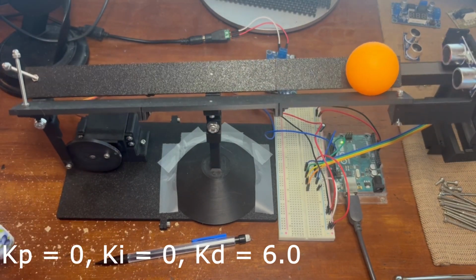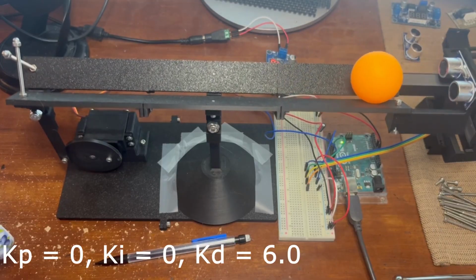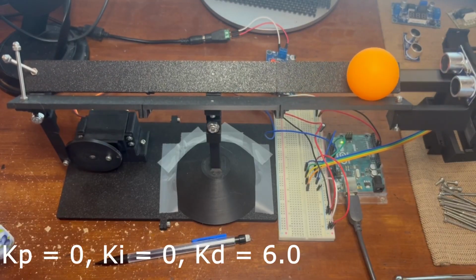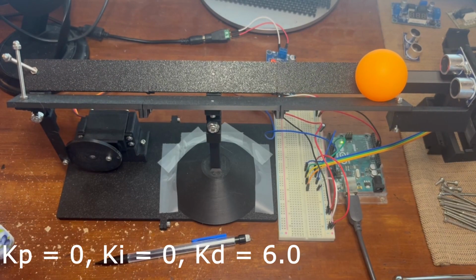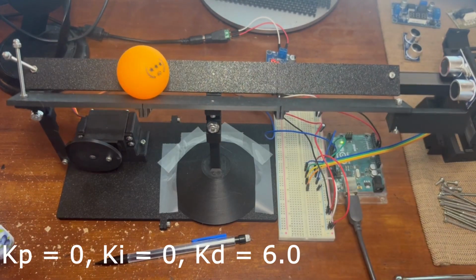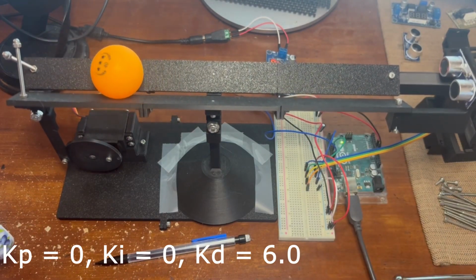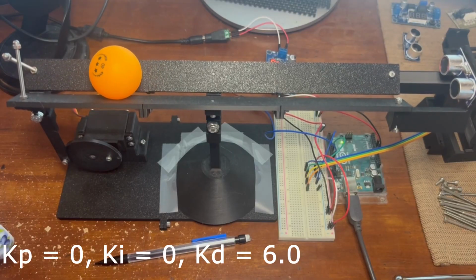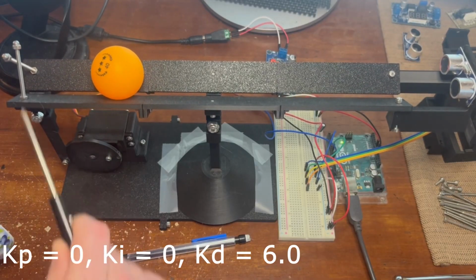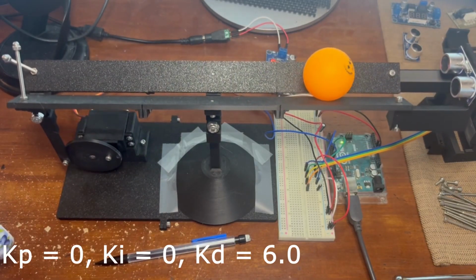This term is very useful when you want to use a relatively large proportional gain, perhaps for a faster response, or your system is subject to step inputs from external forces. However, systems can often become unstable when the derivative term is tuned too high, in other words, when the derivative gain is tuned too high.